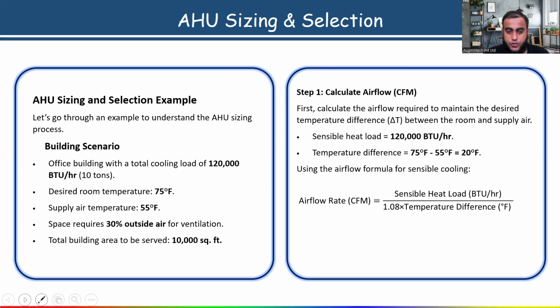Now, just substitute the values. See, the sensible heat load value I have written as 1,20,000, which we have got from the heat load calculation, divided by 1.08 into 20 temperature difference. As per that, I think 5,556 CFM airflow rate we have calculated as per our building scenario. Now, once you get the airflow rate, what is the next thing?